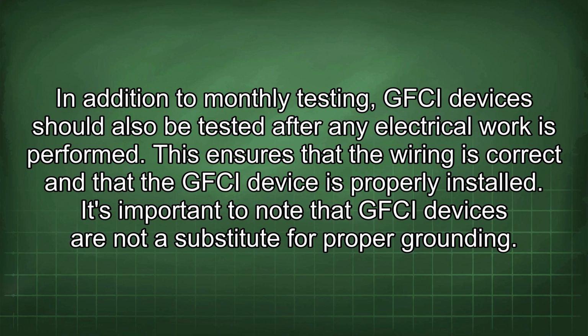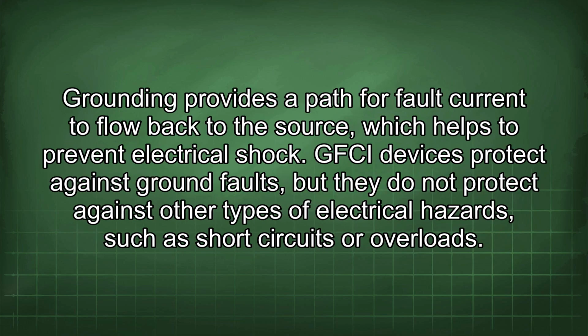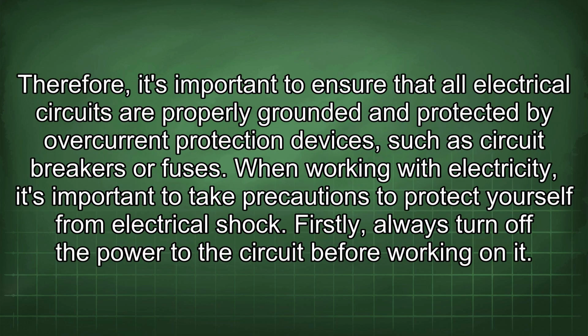It's important to note that GFCI devices are not a substitute for proper grounding. Grounding provides a path for fault current to flow back to the source, which helps to prevent electrical shock. GFCI devices protect against ground faults, but they do not protect against other types of electrical hazards, such as short circuits or overloads. Therefore, it's important to ensure that all electrical circuits are properly grounded and protected by overcurrent protection devices, such as circuit breakers or fuses.